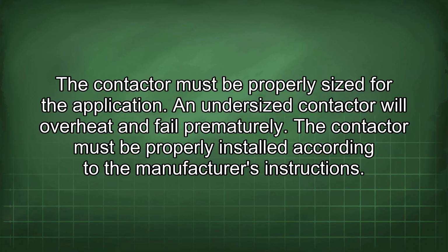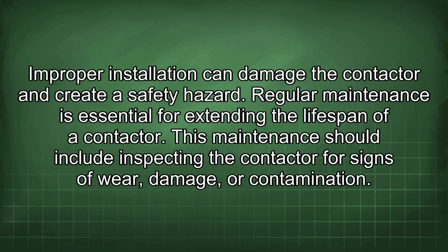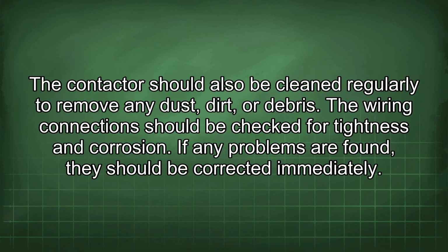The contactor must be properly installed according to the manufacturer's instructions. Improper installation can damage the contactor and create a safety hazard. Regular maintenance is essential for extending the lifespan of a contactor. This maintenance should include inspecting the contactor for signs of wear, damage, or contamination. The contactor should also be cleaned regularly to remove any dust, dirt, or debris. The wiring connections should be checked for tightness and corrosion. If any problems are found, they should be corrected immediately.